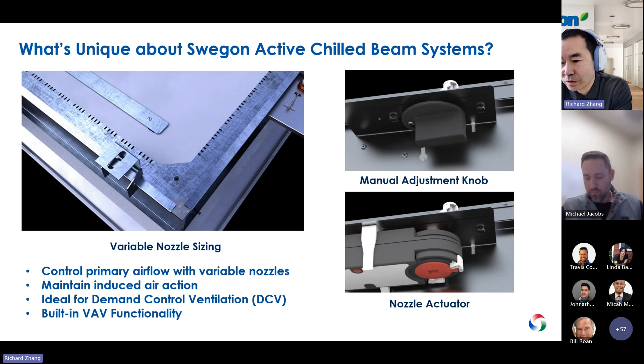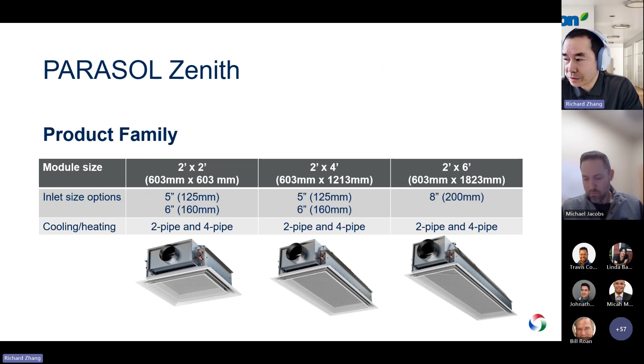Please never exclude that option, because that can be a great candidate for the repurposing of a building. Also, because of the increased capacity of the chill beam, we help simplify the selection of the chill beam design. Instead of having 2x2, 4, 6, 8, 10, and multiple, unlimited nozzle designs for every single constant airflow chill beam, now we limited the size to 3 only. That can be very good news for the designer in the consulting firm. Just imagine if you design a constant flow chill beam system, a decent project will probably make 500 selections. That will reasonably take you 2 to 3 weeks. But for the VAV version of chill beam, you know how many lines? You just need to make 3 selections: 2x2 for 0 to 100 CFM, 2x4 up to 200, and 6 inches for 300 CFM.